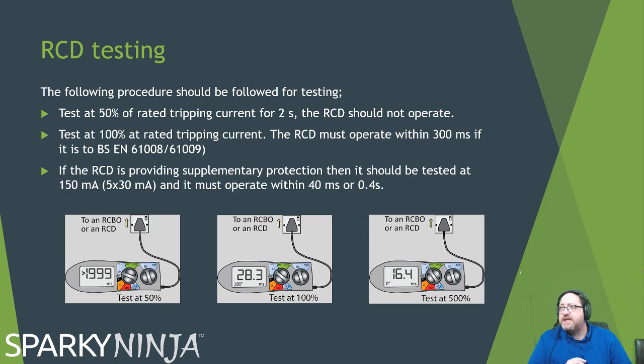Okay, the RCD test. Alright. What you need to understand with RCD testing is done at times half, times 1 and times 5 for every device. So you set the device to the rating of your RCD, 30 or 100. But you do half, you do 1. Understand the maximum times. If it's a 4293 or a 61008 or a 61009, those are all in your on-site guide. Those are all in Guidance Notes 3, 300 milliseconds, 200 milliseconds, etc. You should know those.